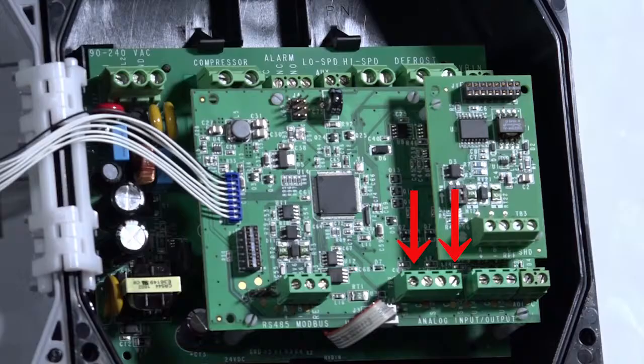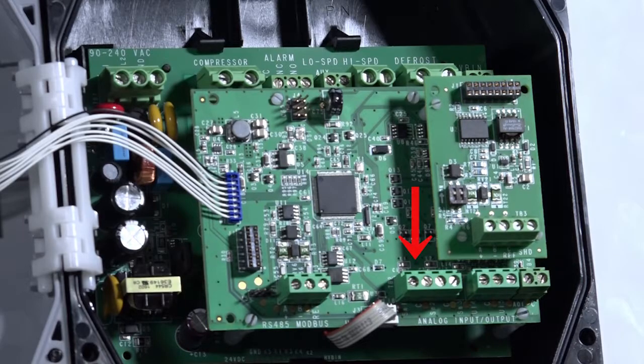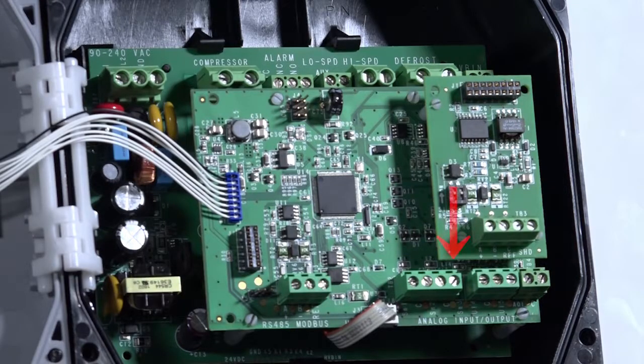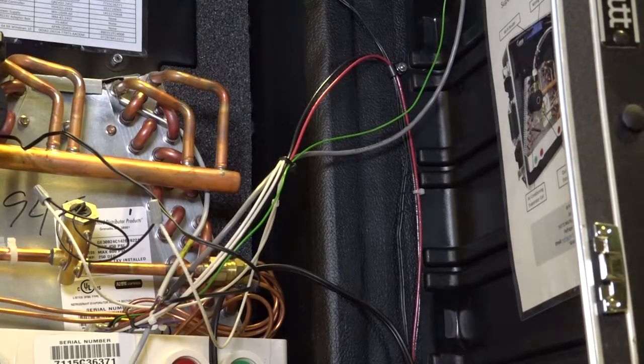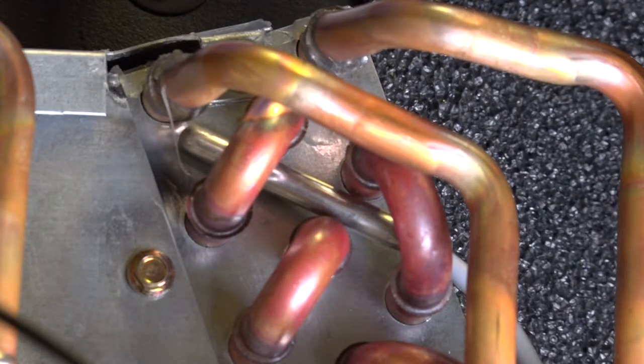The A525 controller has 5 sensor inputs to help control the refrigerated system. These inputs are standard temperature sensors. When setting up the control, you can select either a PTC sensor or an NTC sensor. The first sensor is used to measure the refrigerated space. This is the main control sensor. The second sensor can be used as a defrost termination sensor.